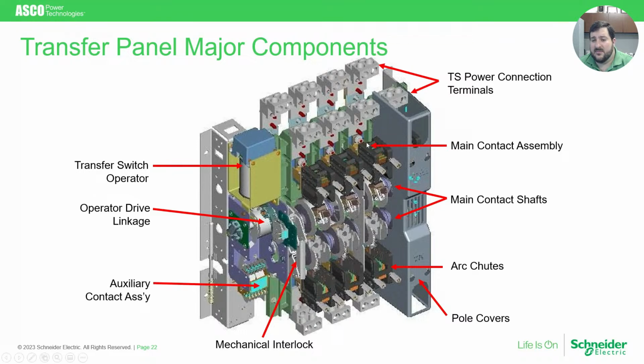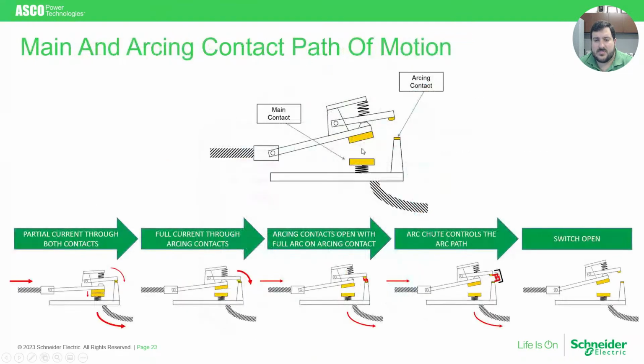We talked a little bit in the video about the contacts and the contact technology used in the majority of our frames, how it's composed of really 2 independent contacts. A main primary contact, which is carrying current the majority of the time when it's feeding the load, as well as an arcing contact, which is meant to take the arc of the equipment and not expose the main contact to that arc during an opening operation primarily.